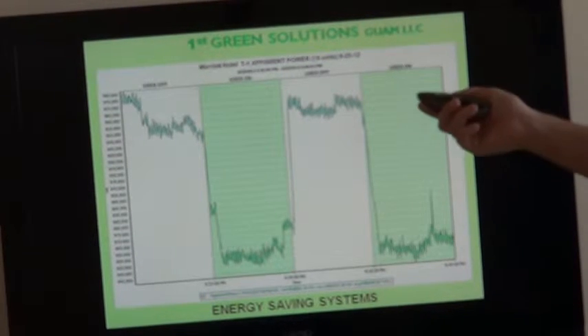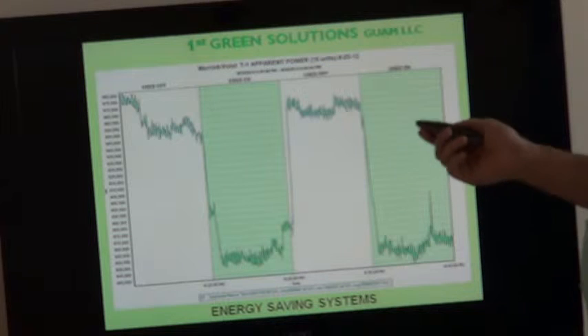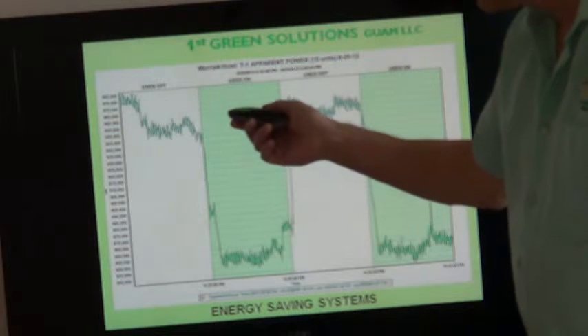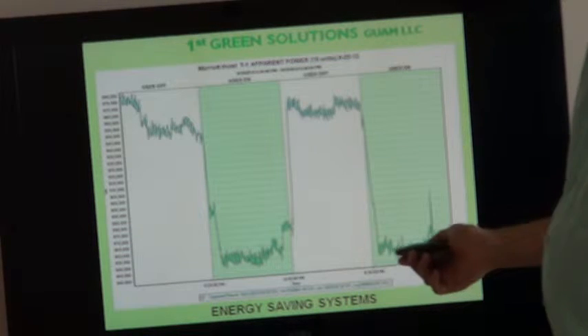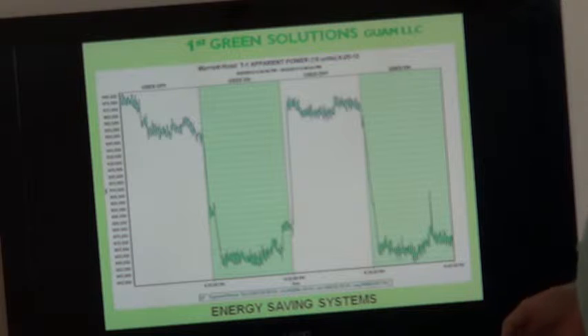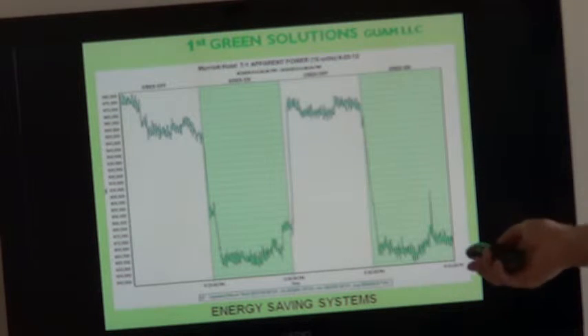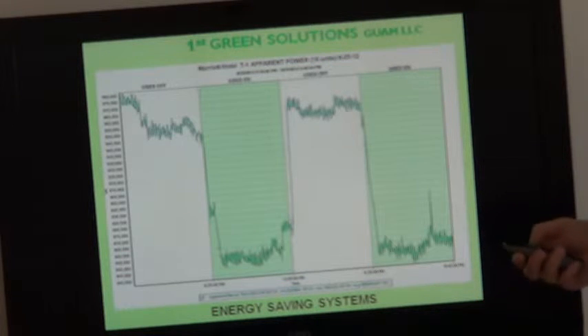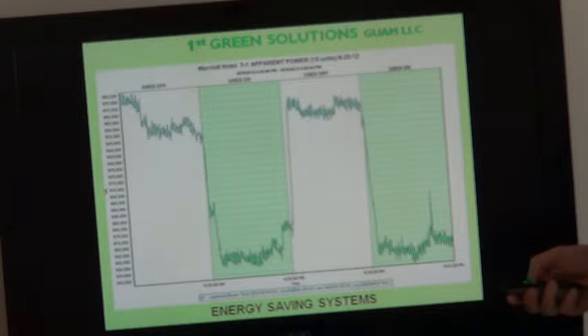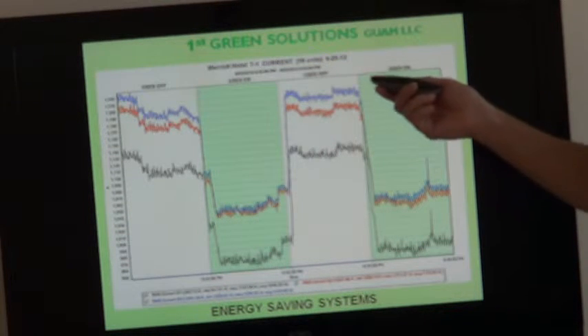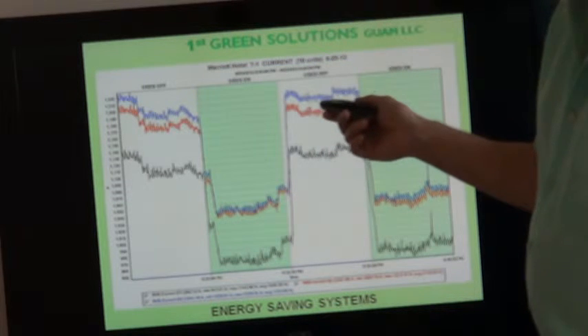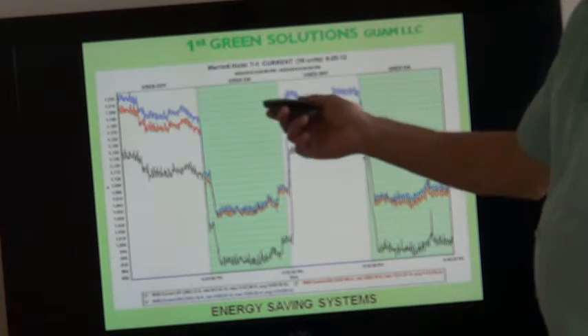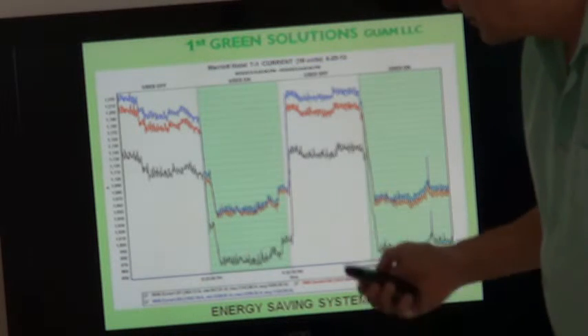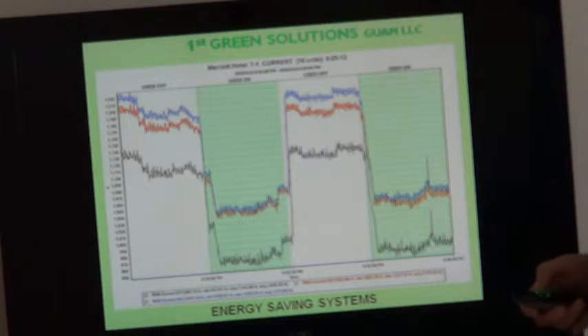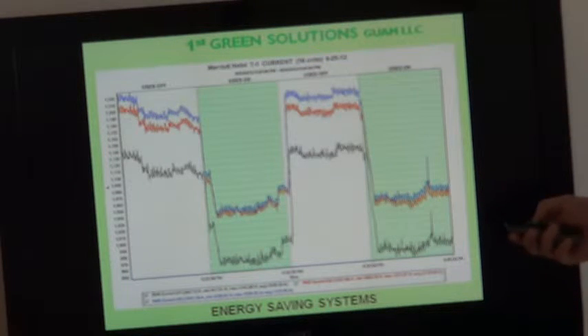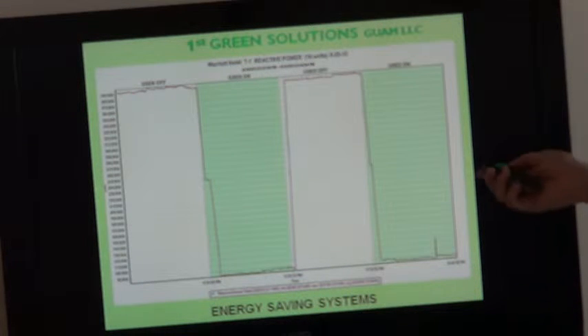On the apparent power, which is the kVA, which is also measured by the utility meter, we're going from the 965,000 range down to the 800,000 range, 850,000. So this represents 105,000 kVA reduction. Current is measured amperage, and right now they're looking at averaging 1,200 amps, dropping down to the 1,040 amps, which is approximately 160 amp reduction. And that is on a per phase basis.